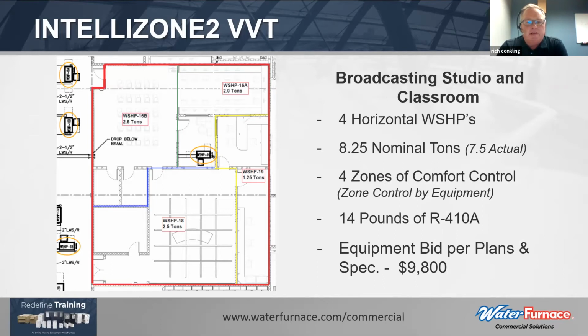You'll notice on the drawing on the left there are three water source heat pumps located in the corridor, circled in yellow, and then one right in the middle in the office, located probably above the desk or the filing cabinet, the two heaviest pieces of equipment in the room. There are 4 water source heat pumps that total 8.25 nominal tons, but there's actually only 7.5 tons of actual capacity required that the engineer scheduled for these spaces.